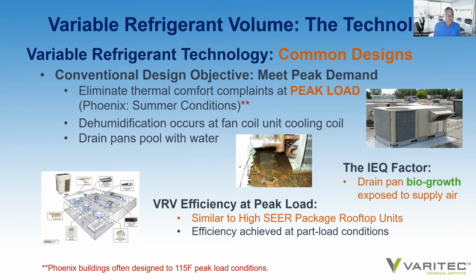So if you design to peak load, be aware you start losing the potential energy efficiency in a variable refrigerant system, because at peak load, VRV systems are not altogether out of line with a high SEER package rooftop unit. VRV systems achieve their efficiency at part load when they can more effectively distribute refrigerant throughout a building to meet the various loads of the various zones throughout the space and avoid the start-stop cycling of compressors or package DX units that we see with more conventional designs.